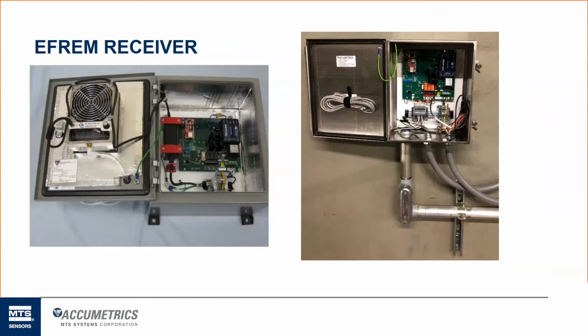To the right, just another example of a non-cooled version and what it may look like installed at a utility. This customer chose to mount this just directly to the concrete bulkhead right below the exciter doghouse. And then they supplied the conduit that ran our coaxial cable up about 80 feet above to the exciter doghouse, and then all the outputs from our system running the other conduits off to the control room. So pretty standard stuff on how we would see our system installed at a power facility.